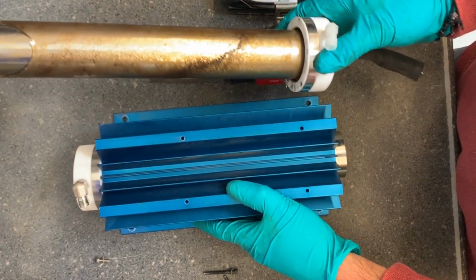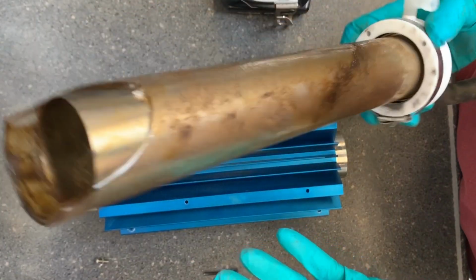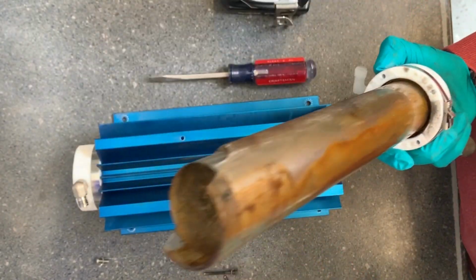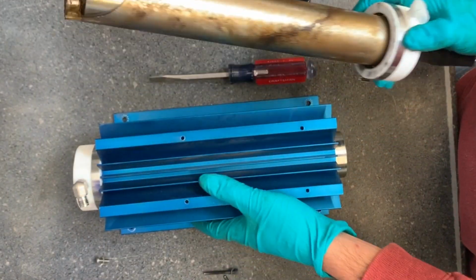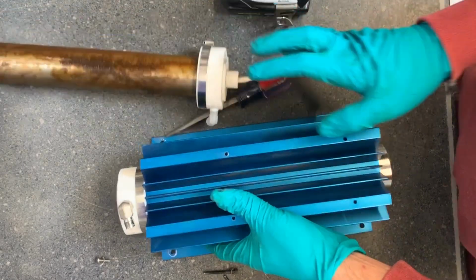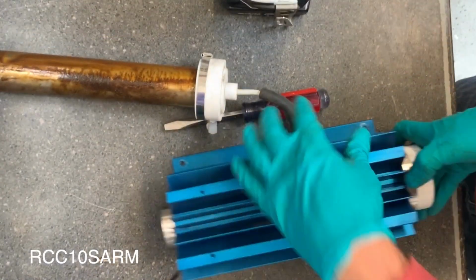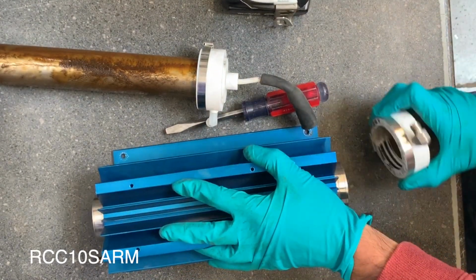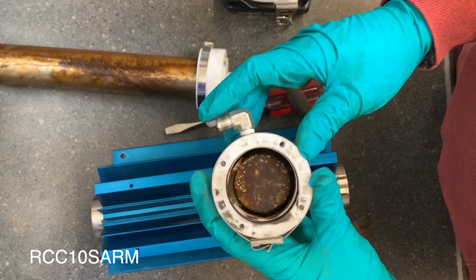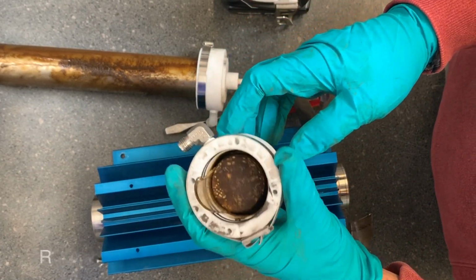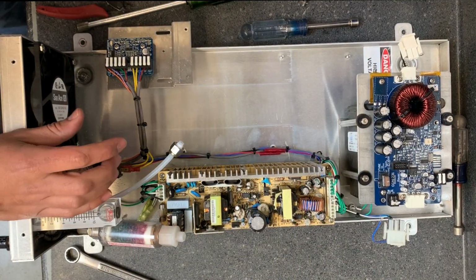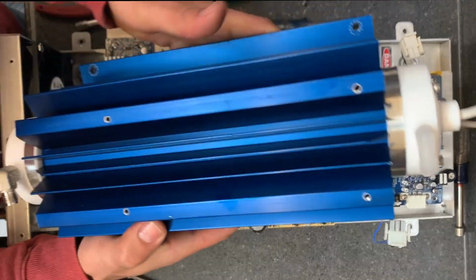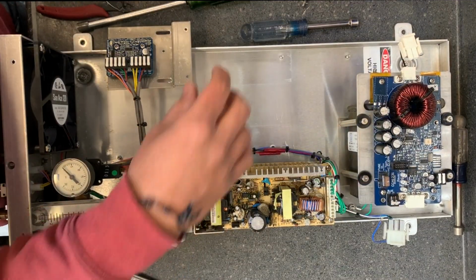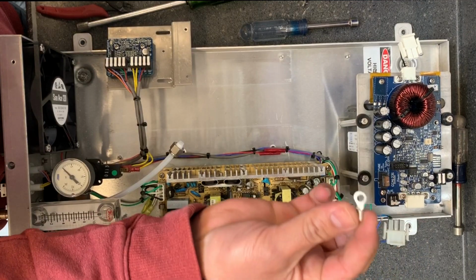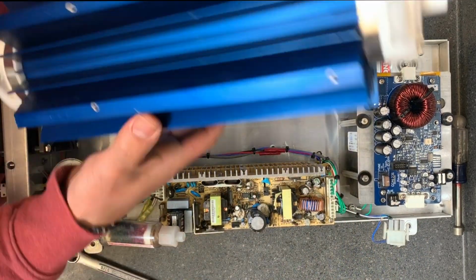So, if you ever do maintenance to a cell that's this dirty and in this bad of a shape, I do recommend going through our core exchange program, which allows you to send in your old core and we'll replace it with the rebuilt core. If you do go through our core exchange, you'll receive a chamber with literature and an extra connector that you're going to use to install it, and this is how you would do it.